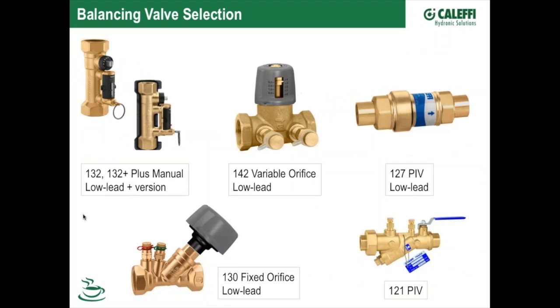Balancing valves, this in itself is a one-hour webinar, but this is a quick overview of what we offer. We've got manual balancing valves, what we call our 132 Quick Setters. The 132 Plus, the plus meaning that that's for domestic water, so we've added a low lead version of that, or lead-free, we call it. Usually low lead is indicated by LF. It can be used on domestic water.